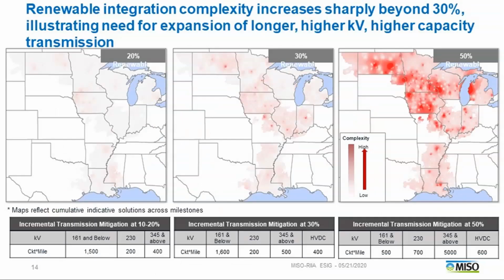Starting to look at the reliability picture and some of the transmission needs of the system, as I talked about earlier, one of our conclusions is that the complexity of integration was increasing sharply beyond 30% of the annual energy share being met through renewable energy. This is starting to illustrate the need for longer and higher voltage transmission lines. You can see from the pictures here that at lower levels of renewables, the issues we're seeing, as well as the transmission needs, are relatively low.